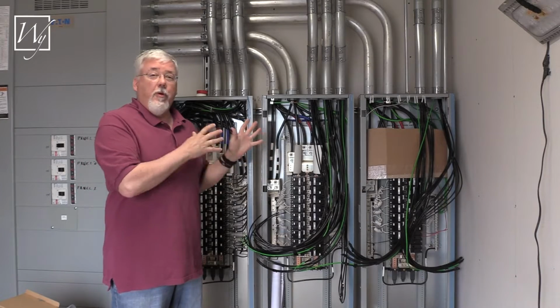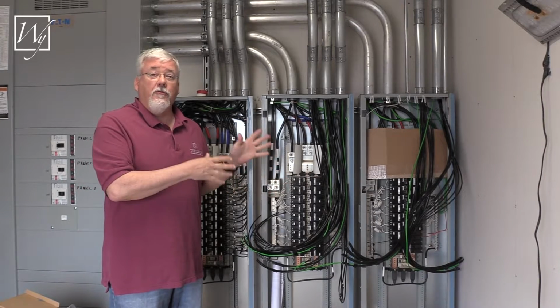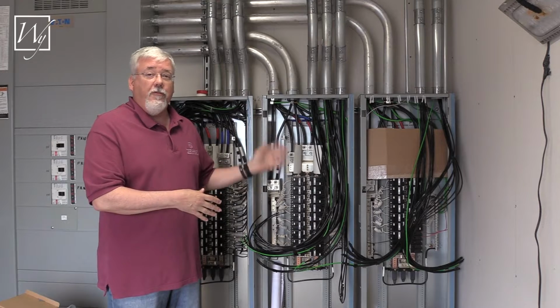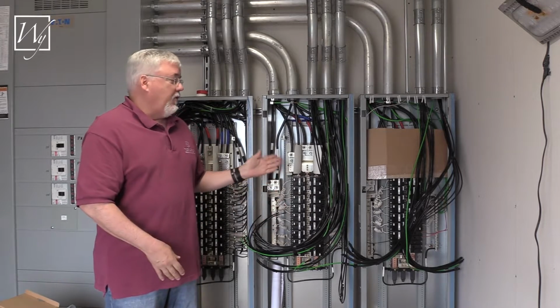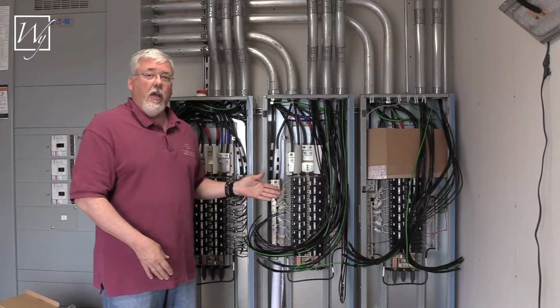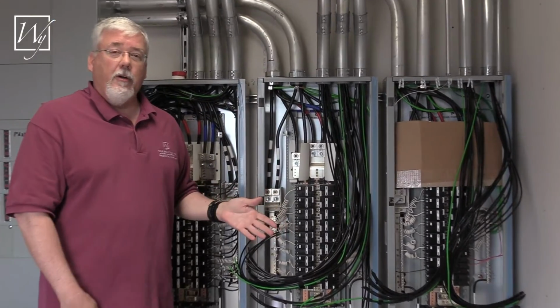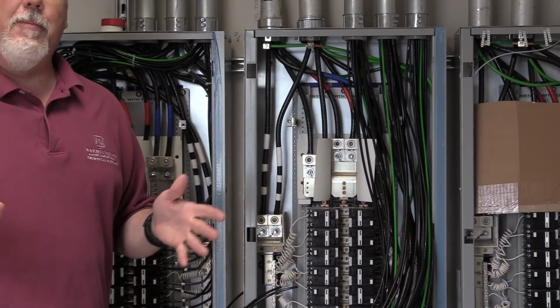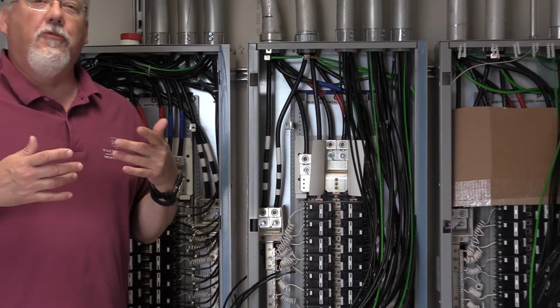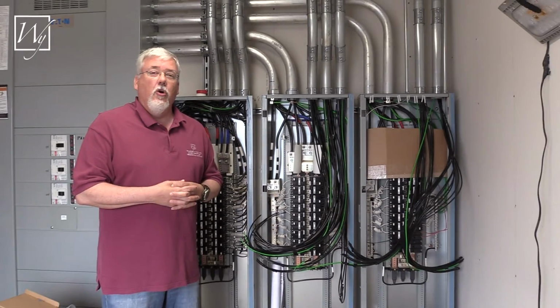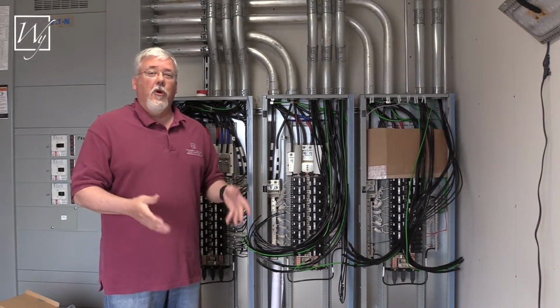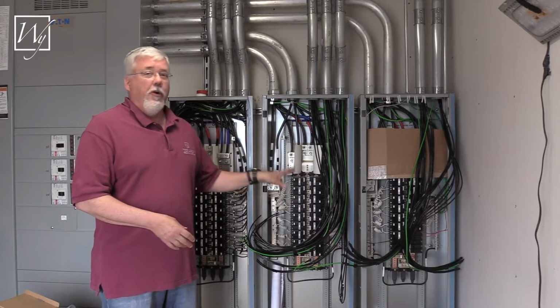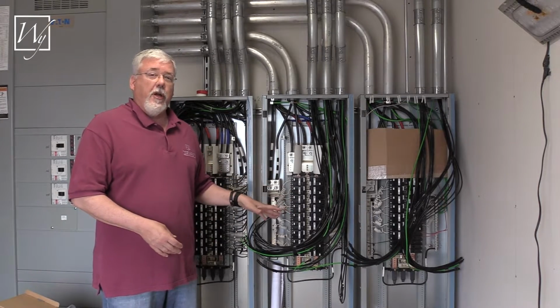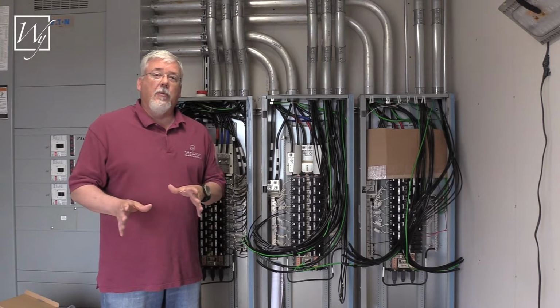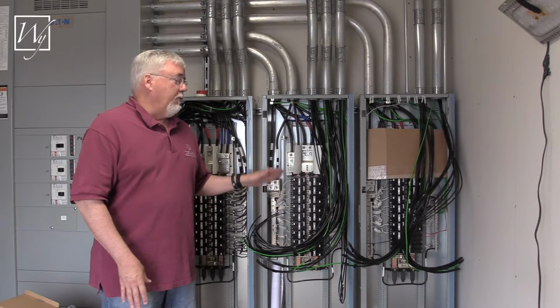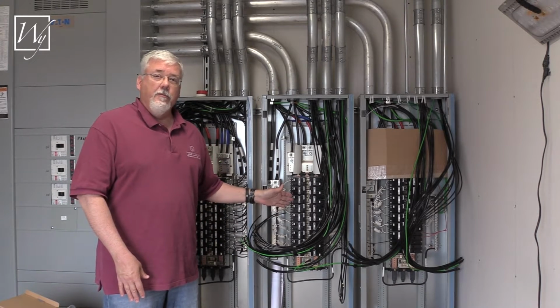Here we can see our breaker panels for this job, and this is a very large installation. There are 35 breakers installed, and if you take a quick look at them, you can see that they are GFEP breakers, or your local name may be GFPE, ground fault equipment protection, or ground fault protection for equipment, however you want to word it. They're 30 milliamp trip, they're a special circuit breaker, and any snow melting job that is being done outdoors will require this type of circuit breaker.